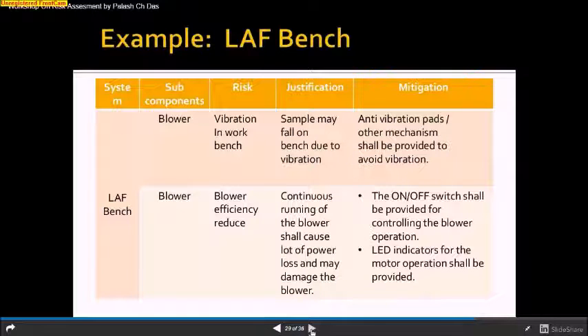If there is a possibility of a timer, the timer will indicate with an alarm that the machine is ready. In the case of LAF, what is most recommended is that you should have an established recovery timing. Once you switch off the LAF and switch it on again, when should you use the LAF? So you validate the recovery timing and put it into the system. Suppose it is 15 minutes. Once you switch on the machine, it will automatically count the 15 minutes. When the 15 minutes is done, the machine will give an alarm and show that yes, you can use the bench right now. Rather than documenting in your logbook that I started at 7 o'clock, then at 7:30 I have done analysis, it is a better approach. You should have a control in the LAF.